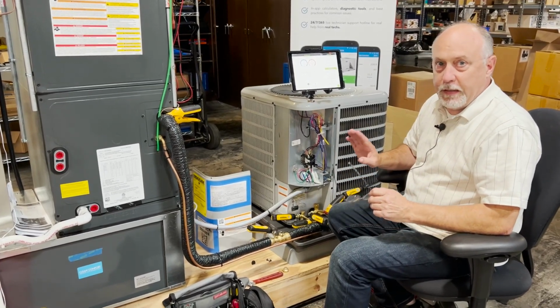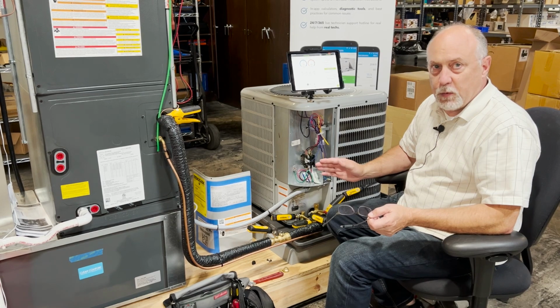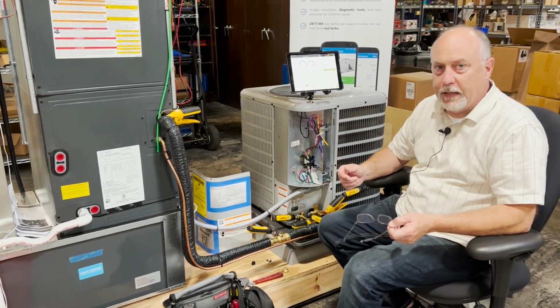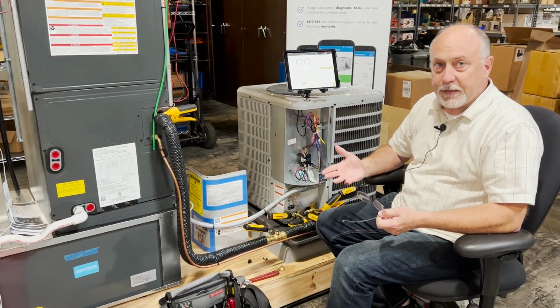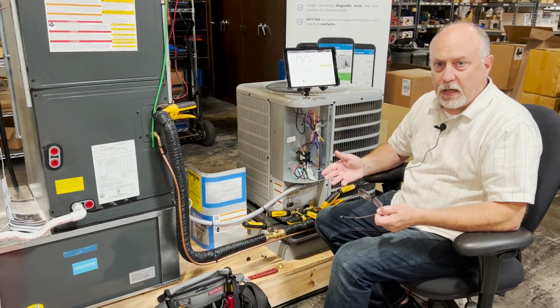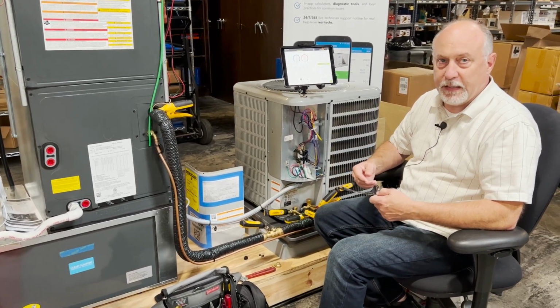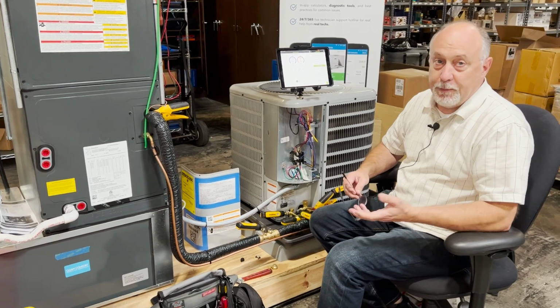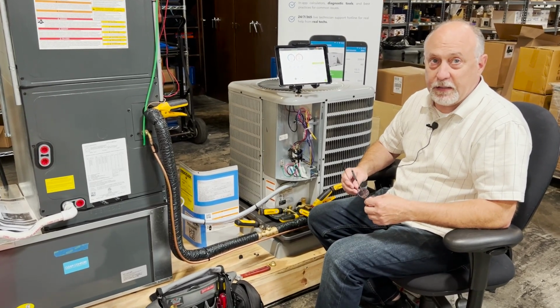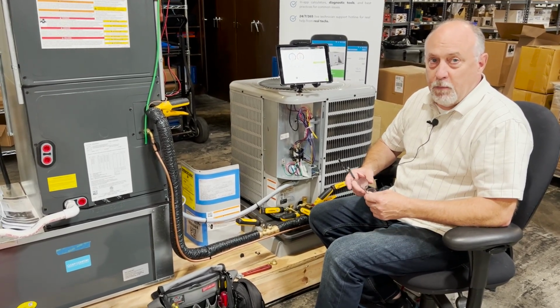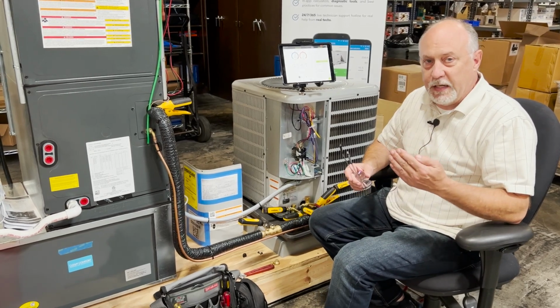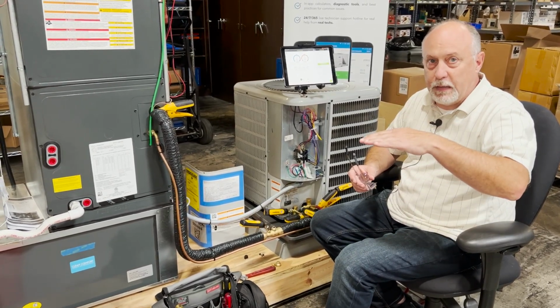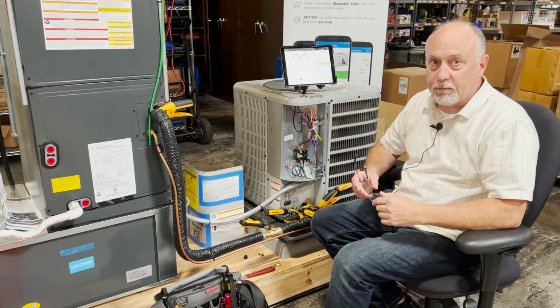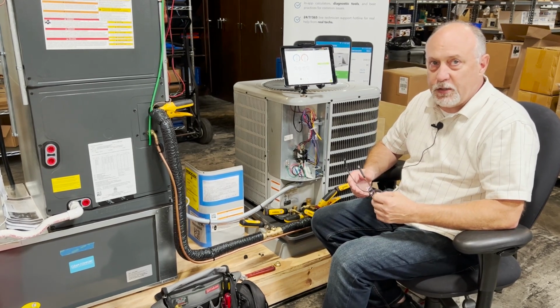I wanted to show you a new diagnostic we built into measureQuick. One of our customers called the other day and had a restricted suction line, and they said the software didn't pick it up. They were sort of surprised we didn't have that diagnostic built in, and to be honest, I was too. It's not a condition that we run across all the time. But in new construction, when the equipment starts to settle, maybe it gets kinked off or something, and it's actually a pretty challenging one to pick up.